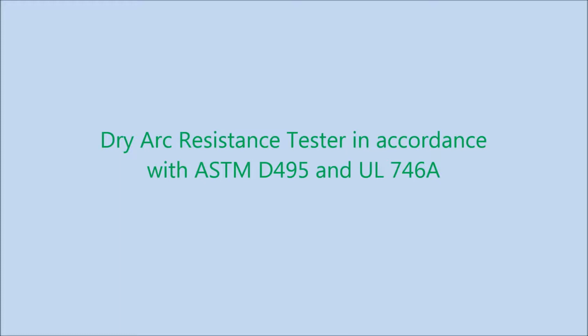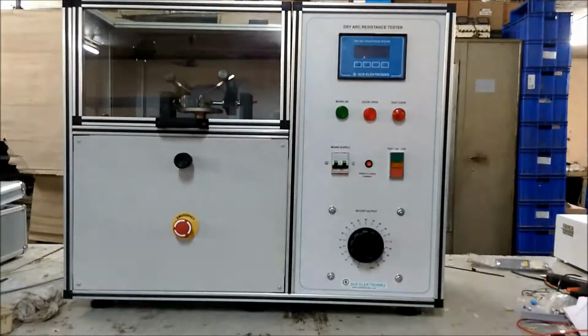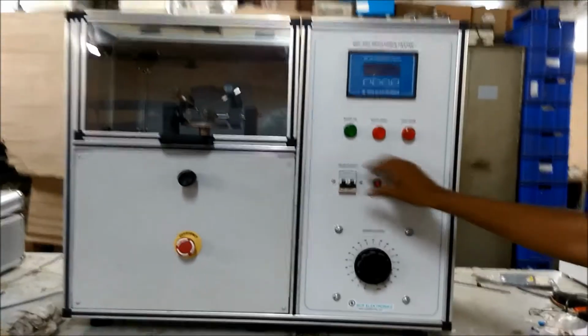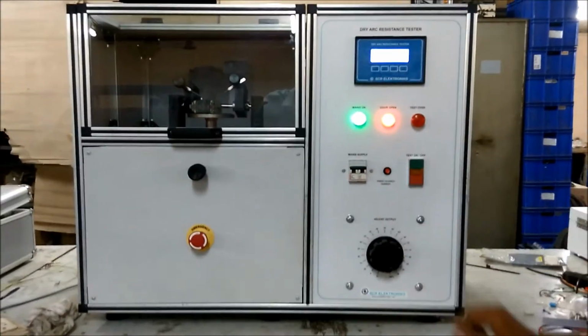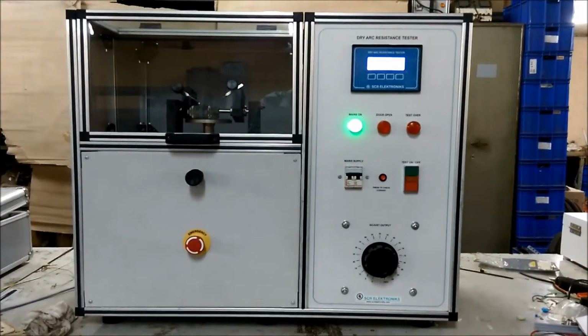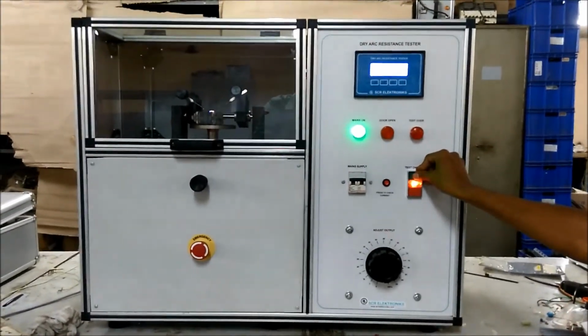Dry arc resistance tester in accordance with ASTM standard D495 and UL746A. After adjusting the voltage to 12.5 kV, press on test on to start the test.